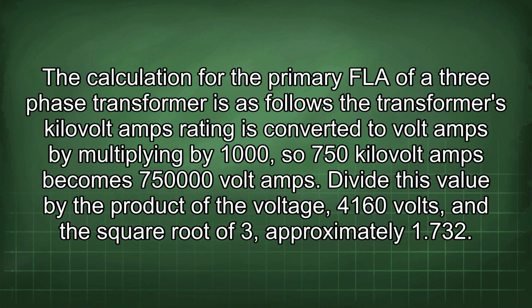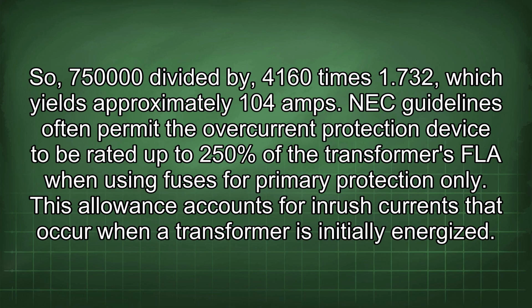The calculation for the primary FLA of a three-phase transformer is as follows. The transformer's kilovolt amps rating is converted to volt amps by multiplying by 1000, so 750 kilovolt amps becomes 750,000 volt amps. Divide this value by the product of the voltage, 4160 volts, and the square root of 3, approximately 1.732. So, 750,000 divided by 4,160 times 1.732, which yields approximately 104 amps.